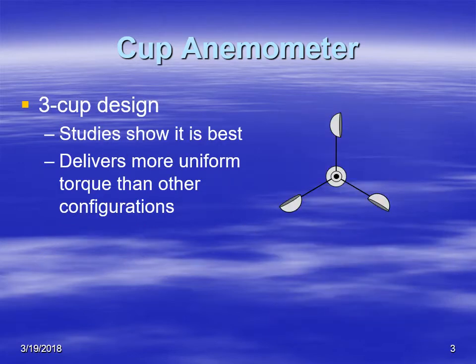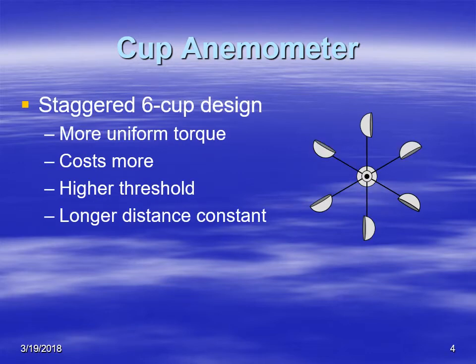The 3-cup design is a good design. It's probably the most common that you see. Studies have shown that it's the best. It produces the most uniform torque of the configurations. But you'll also see 4, perhaps 6-cup designs, where you have, of course, more uniform torque because there are more cups. However, adding cups adds weight, so that means that you're going to have higher threshold wind speeds and also longer distance constants. And of course, the more cups you add, the more expensive it gets.